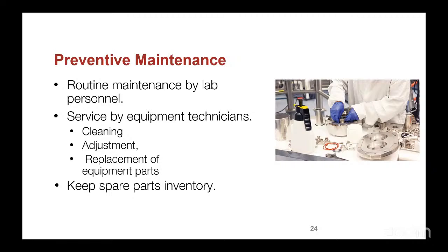And some of us, when we talk about those maintenances, we allow the maintenance to be due before calling them. You have to know your lead time. The time it takes them. Maybe if they need to get a particular part, they need to order those parts. If the part is not readily available within the lab, you need to keep it. So that's the responsibility of the lab management to ensure that these things are being done.